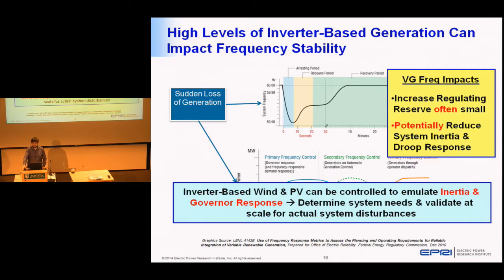You can, though, now, and GE in particular, particularly for wind, can provide emulated inertia through its power electronics. Essentially it borrows a small bit of energy from the rotating mass of the wind turbine and pushes it back out onto the system. You do have that payback period later on, a few seconds later, where the wind turbine then slows down again. So you do end up having something a little bit different from the normal way that conventional generation provides this, but it can be done. Solar, you might need some storage to help you do that, but it can, or else you can curtail the solar a little bit, a few percent below, and then if something happens, push it on. So both of them can be done.